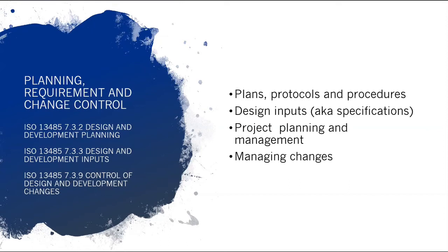Engineering procedures, procedures for design reviews, items such as risk management need procedures, documentation control, configuration control. So it really covers the whole gamut. And protocol? Well, a protocol is more a specific step-by-step way of doing things. So, for example, if you're undertaking verification testing, the protocol for that defines the specific steps that you follow. It is in the form of a procedure, but it is specific to the particular device. So it's a little more specific than what you'll find under your general quality system and standard operating procedures.